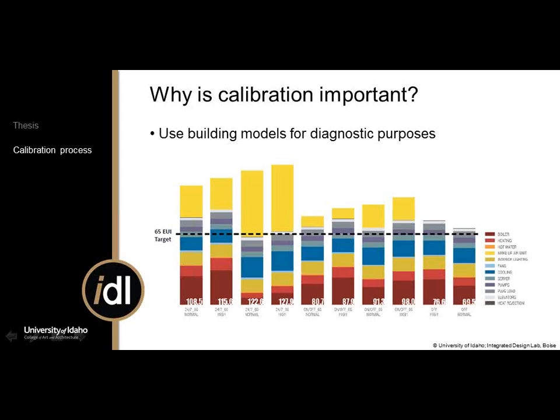So this example is of an office building that we worked on where we didn't quite understand how the makeup air unit was operating. We had heard different accounts from the building operations manager, from the HVAC technician, and from the tenants themselves on how much fresh air was being admitted into the building, and what the set point was for that fresh air. It was a makeup air unit, so it was providing fresh air to heat pumps, and what the schedule was. Do they run it all the time throughout the year? Do they run it in the summer but not in the winter, and so on and so forth?